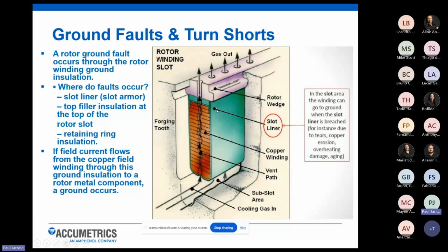So if this material gets worn down and causes a break or a hole in the material, now the current that would normally pass through the copper bus bars will leak out and start to cause damage to the rotor itself. If you get two faults that develop along the rotor, that is a very significant and damaging case, where all your current that's supposed to be flowing through the field windings is now diverted directly into the rotor forging itself. You can superheat the rotor, cause it to warp and have massive vibration issues, as well as burning and damage from that current arcing into the rotor.